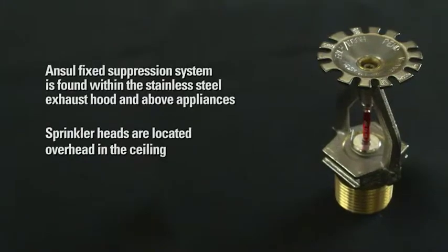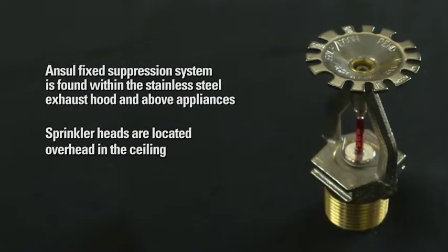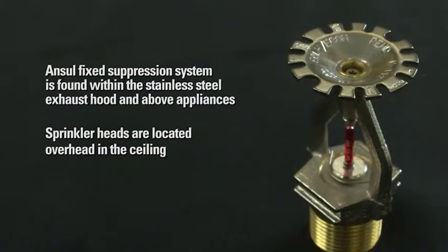Many facilities are equipped with a water-based sprinkler system. The sprinkler heads are overhead, sometimes exposed and sometimes concealed. The heads themselves will only activate when the temperature reaches a determined point, normally 135 degrees to 170 degrees. Only the affected heads will activate. The entire network of sprinkler heads will not automatically activate. There is no manual means of activation.